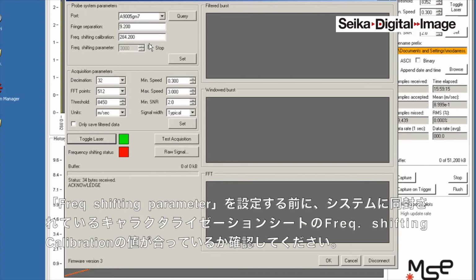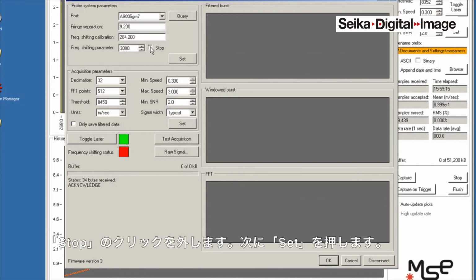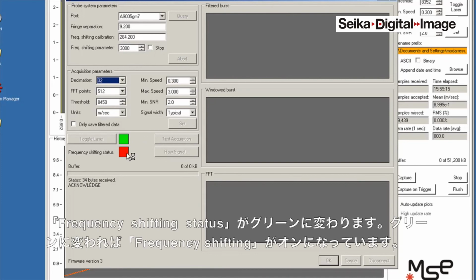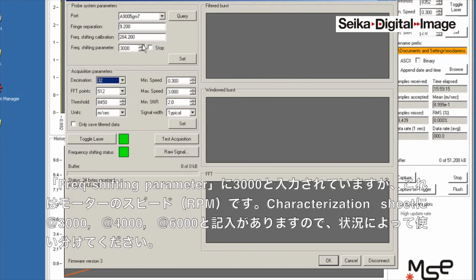To set up the frequency shifting, make sure that the frequency shifting parameter or the calibration number is correct according to the characterization sheet. Unmark the stop and push set. And once you do that, the frequency shifting status should turn green, and that means the frequency shifting has started and is correctly set at this number. You can use numbers from 3000 RPM, which is the speed of the motor, to about 10,000 RPM. Each one will give you a different amount of shifting that is provided in your characterization sheet.